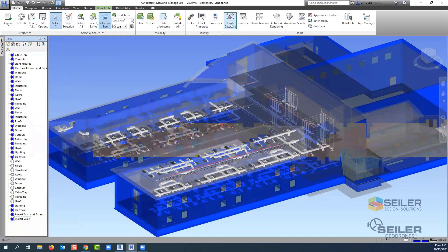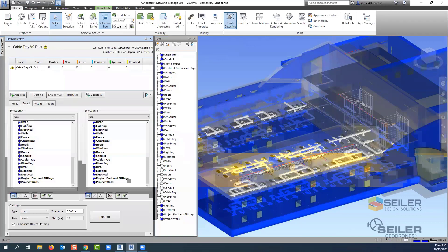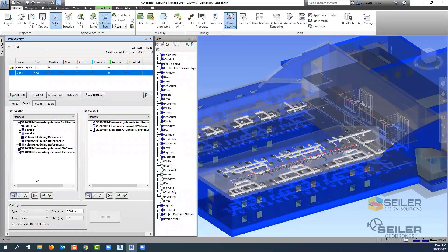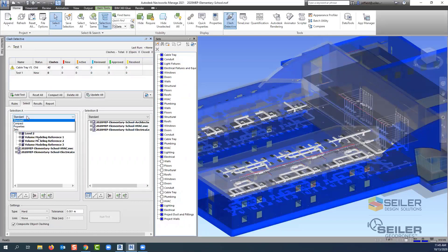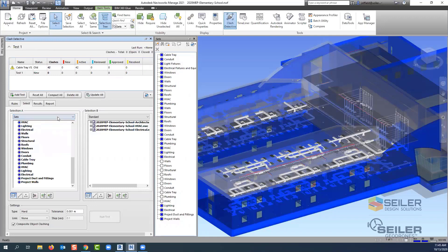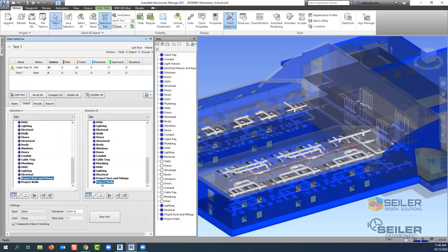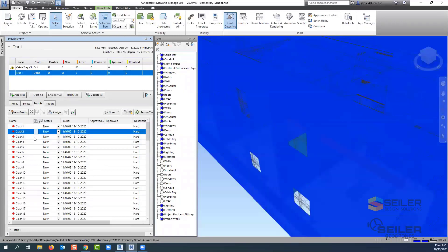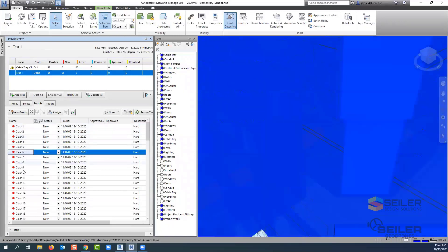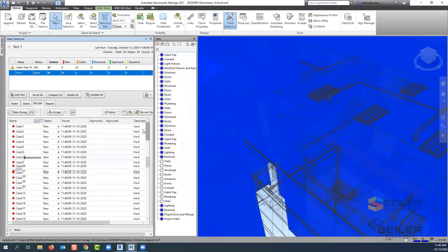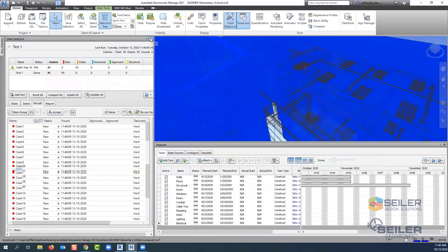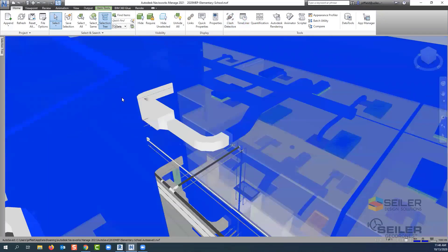Once that is set, now if you wanted to run a quick collision detection, we can come up here, add a brand new one. And instead of breaking apart our files like we typically could within the project, here where it says standard under selection A and B, this is where we're going to pick sets. And so now we can run these sets against each other. Of course, we have other additional tools. But as soon as we hit that, now we've got our clashes based off those fittings for the ductwork, the fittings, and also the walls. So we can see here as we move across through here where those particular items are located. So you can also export this out, but you can also use it for Timeliner down the road. See how you can use the selection sets for those particular items in there. So it's a lot of flexibility and additional features that you can use for those particular tools.